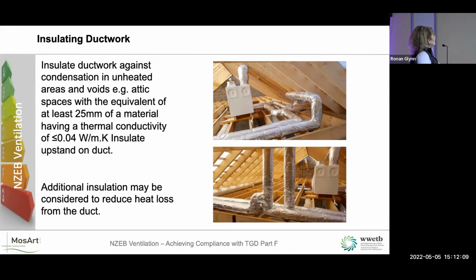So it says here as well, additional insulation may be considered to reduce heat loss from the duct. So again, if that's an MVHR unit, you're trying to hold on to that heat. You want that heat going into your supply rooms. If you're sending it up into the attic, you have to insulate the whole lot to try and keep the heat in the ducts. Now, you want to be running your ducts as well from A to B.